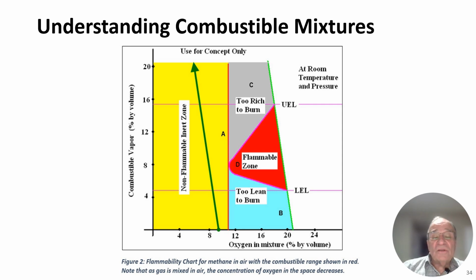One of the things that you have to watch out for when you're purging large tanks is that you don't have channel purging, which means that your purge gas goes up in a channel and you're reading the outlet as being purged well enough, let's say down to 9% oxygen, but there are pockets within the tank that might have 11, 12% oxygen. You want to make sure that that doesn't occur, and there are different ways to do that. Let me just talk for a moment about exhausting a large tank that's filled with gas and you want to purge that large tank out. Typically, you have vents that are used, and you have a large vent on the top of the tank, might be 16-inch in diameter.